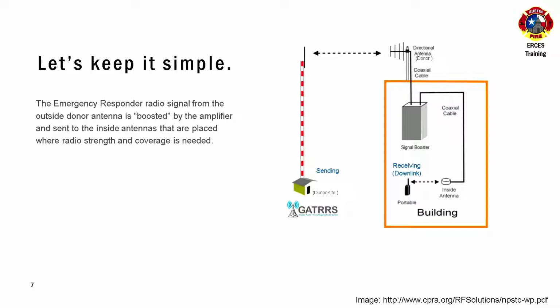You can picture someone inside the building using a portable radio. What happens is the signal goes into the building through the antenna on the roof installed for that purpose, goes to the booster - think of it exactly as that, it boosts the signal - and then goes through cable to the inside antennas. Basically you're just retransmitting the signal from outside the building that was too weak or unable to penetrate the building shell.